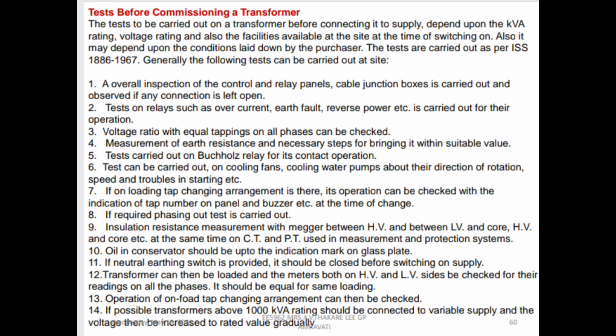First is an overall inspection of the control and relay panels. Cable junction boxes are inspected to observe if any connection is left open. Second is test on relays such as overcurrent, earth fault, reverse power, etc., which is carried out for their operation. Third, voltage ratio with equal tapping on all phases can be checked. Fourth is measurement of earth resistance and necessary steps for bringing it within suitable value. Fifth is test carried out on Buchholz relay for its contact operation. Sixth, tests can be carried out on cooling fans and cooling water pumps for their direction of rotation, speed, and troubles in starting, etc.